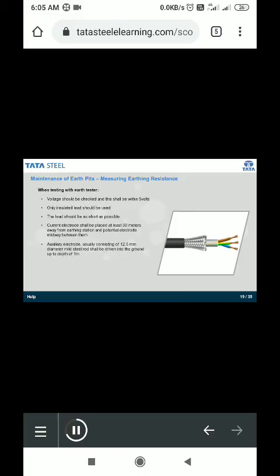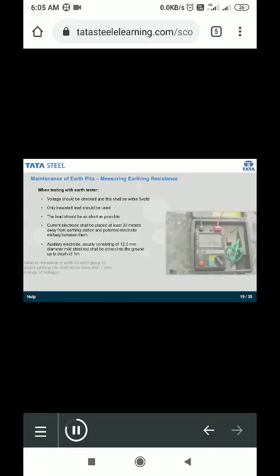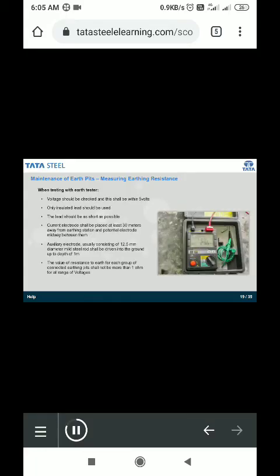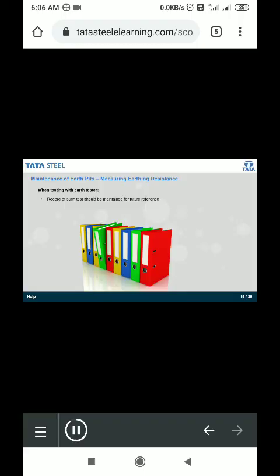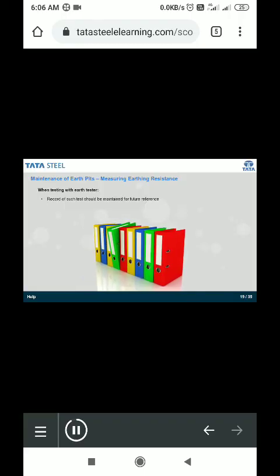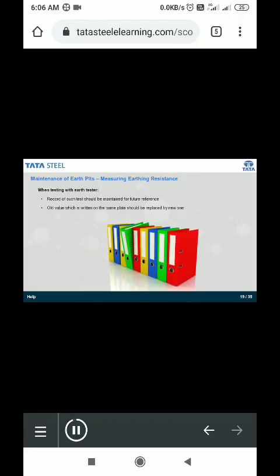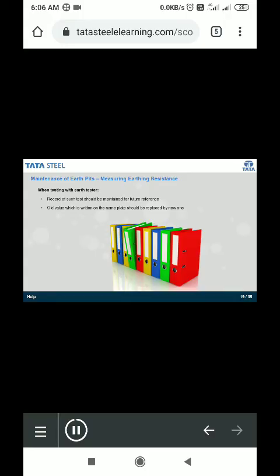The auxiliary electrode, usually consisting of a 12.5 mm diameter mild steel rod, shall be driven into the ground up to a depth of 1 meter. The value of resistance to earth for each group of connected earthing pits shall not be more than 1 ohm for all ranges of voltages. A record of such tests should be maintained for future reference. The old value, which is written on the nameplate, should be replaced by the new one.